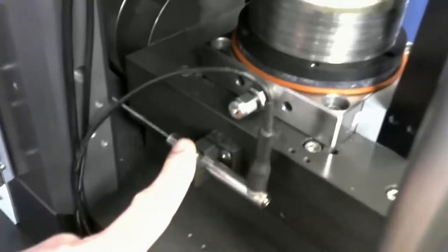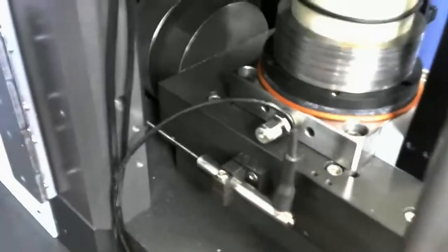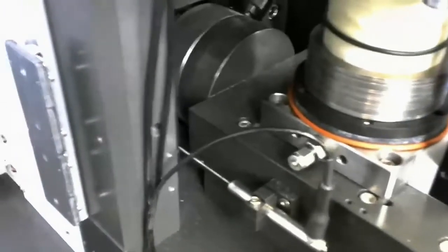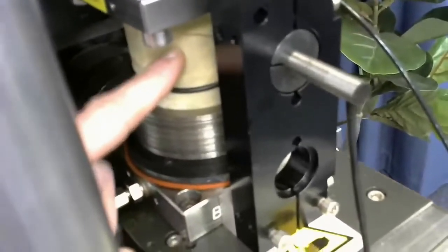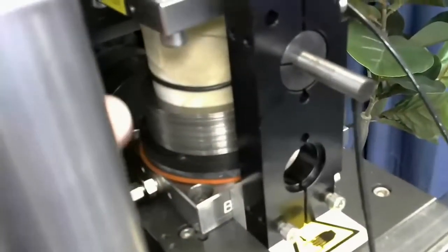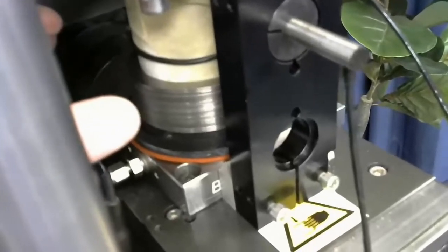Inside here we have a primary horizontal shear LVDT, and then similar to the vertical axis, we use the encoder for a secondary. Fitted on the front here is our top cap LVDT upgrade. This measures directly off of the top cap, so any slight movement in the top cap is taken into effect, which reduces the compliance even further on the machine. Again, the vertical LVDT upgrade in here is a more localized measurement, better for compliance.